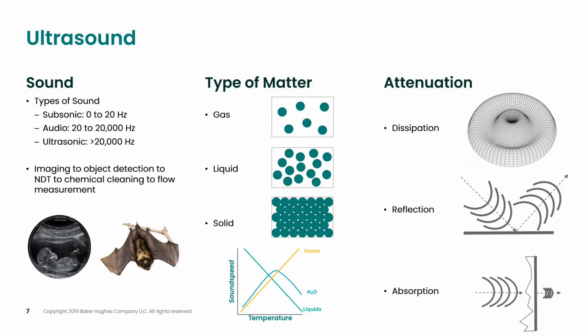Reflection occurs when a sound wave bounces off an object. In ultrasonic flow measurement, we can actually bounce a signal off of the outside of the pipe to get a measurement. However, second phase materials, such as gaseous bubbles in a liquid stream, can cause some signals to bounce away in a different direction than what is expected.